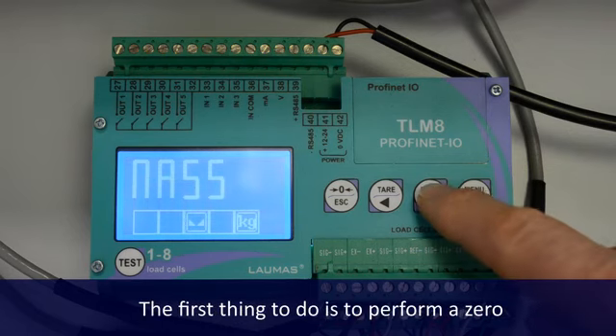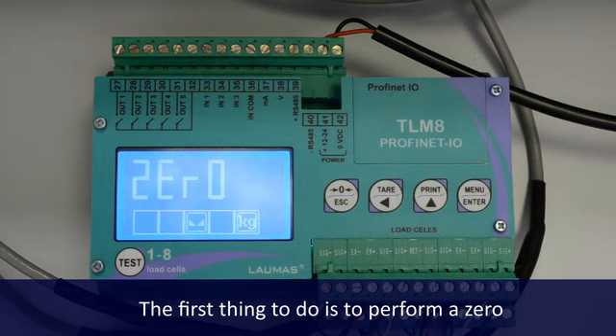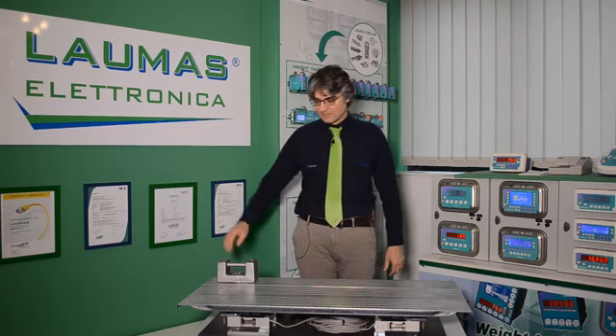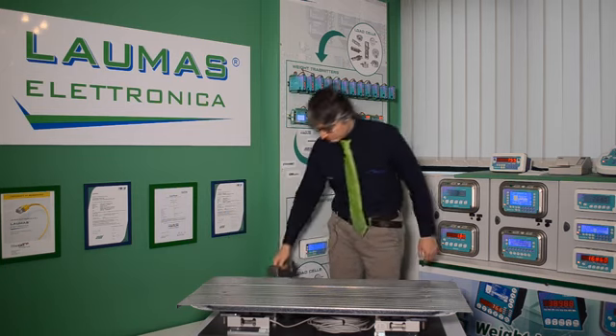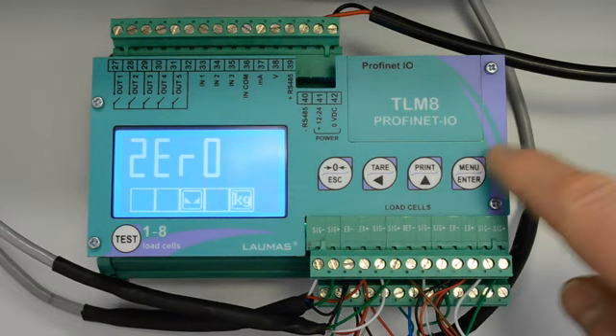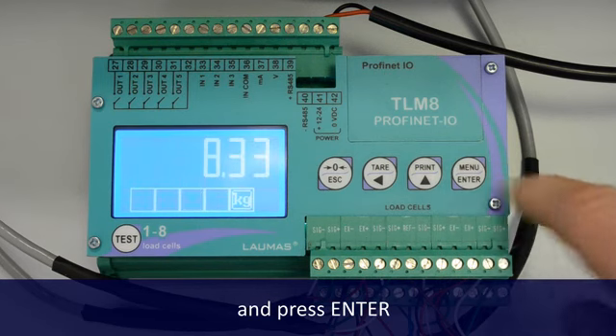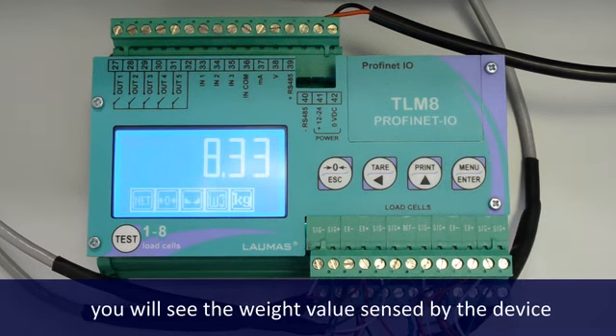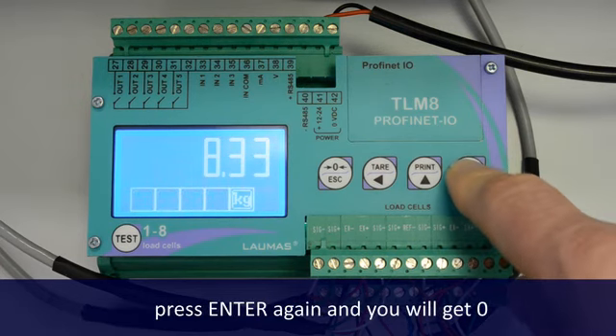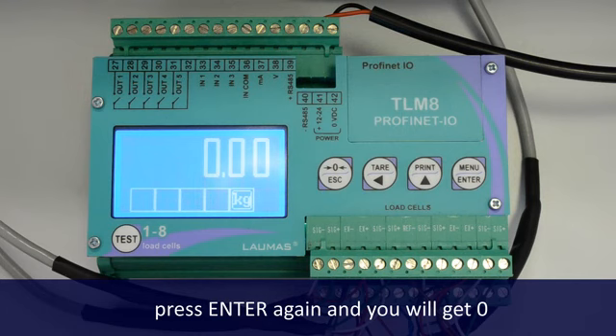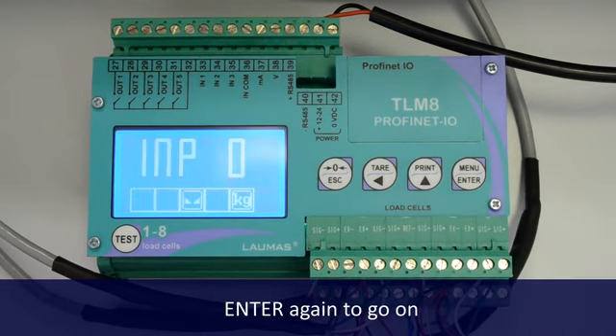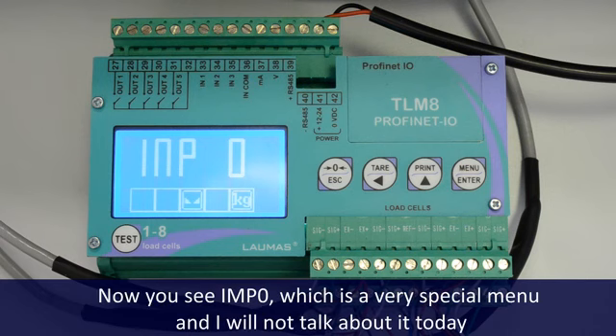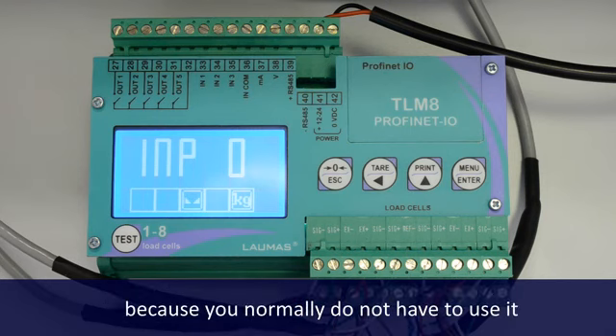The first thing to do is to perform a zero. So unload the platform and press Enter. You will see the weight value sensed by the device. Press Enter again, and you will get 0. Enter again to go on. Now you see INP0, which is a very special menu, and I will not talk about it today, because you normally do not have to use it.